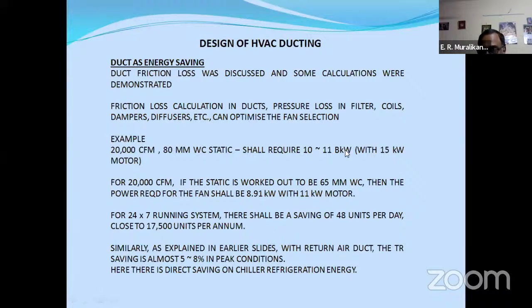Instead of 11 kilowatt, we'll be spending more. These are the consequences of opting for wrong selection of fans. For the same case, if I'm running 24/7, there will be a saving of 48 units per day, close to 17,500 units per annum. So you can imagine what the cost of this will be. If you have multiple fans working this way, can you imagine what the saving will be? We already spent on over design by putting a 15 kilowatt motor and then keep burning energy. If you optimize to an 11 kilowatt motor at the design and project stage and run at this, you have a good saving.